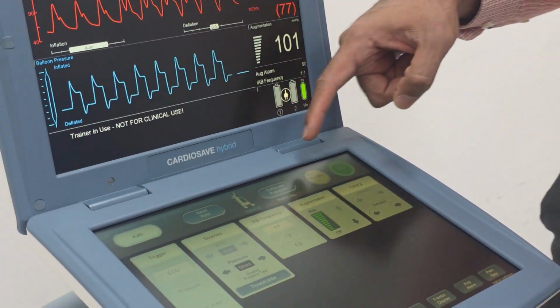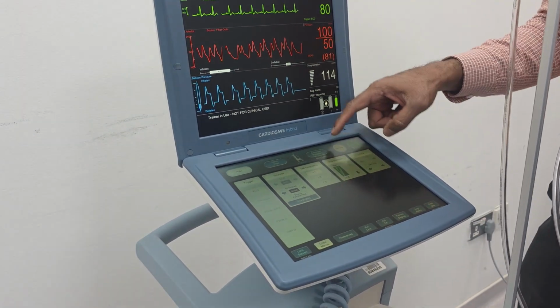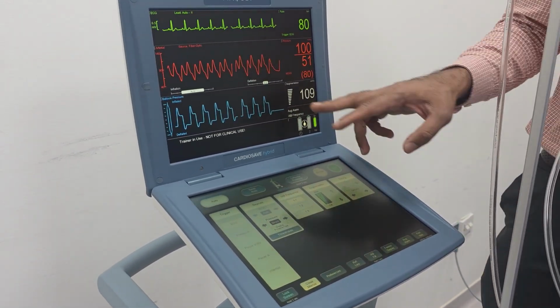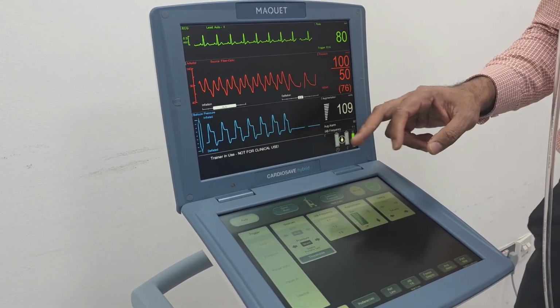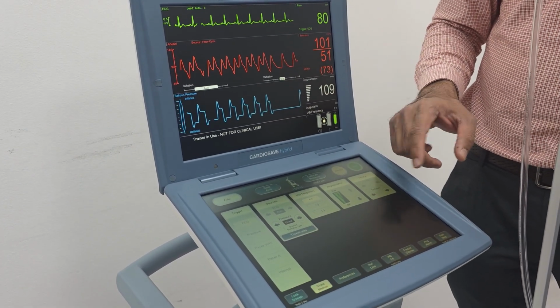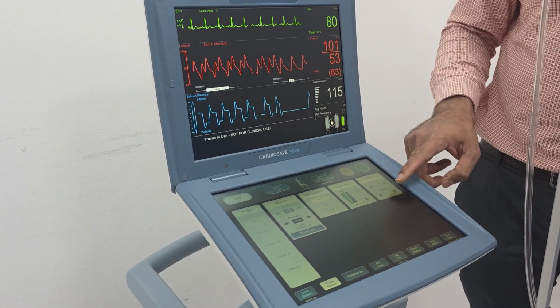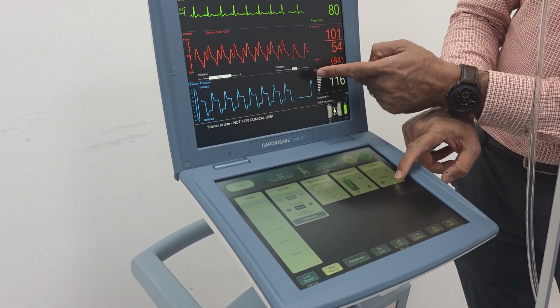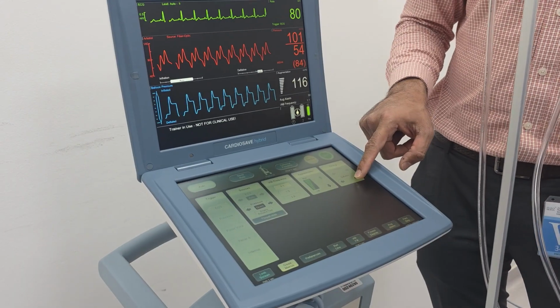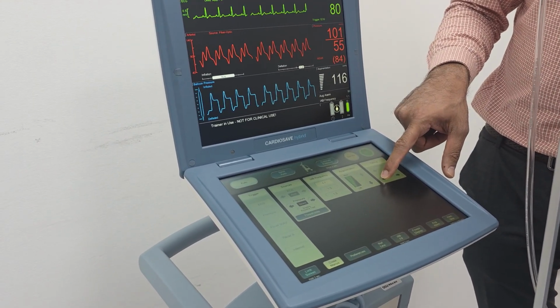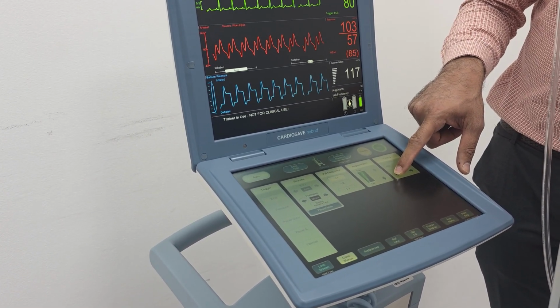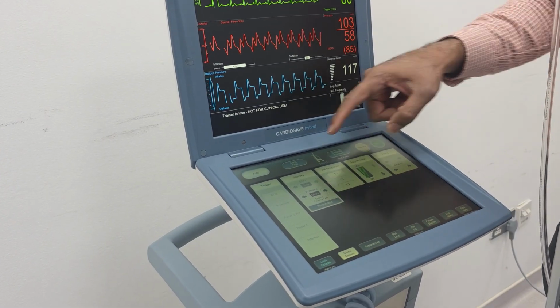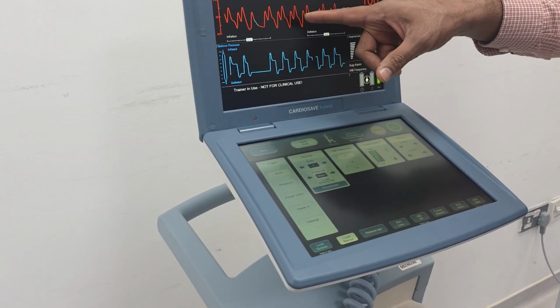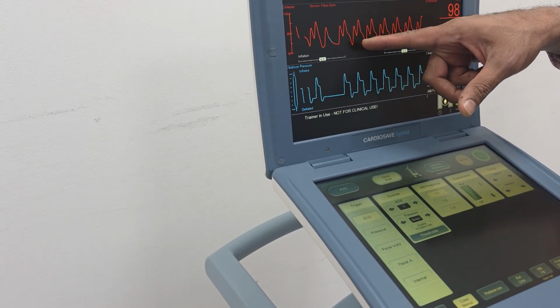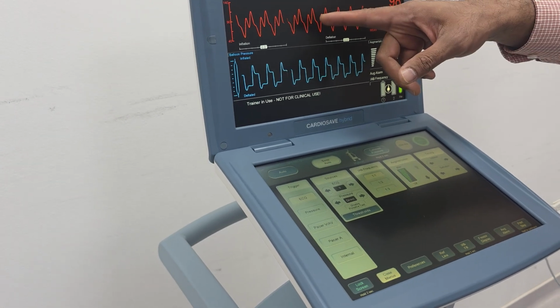Now I will go to auto mode again. In auto mode, you don't have any control on the timing. See, both are in auto. When to inflate and when to deflate, the machine is controlling automatically. But in auto mode, you can still control the deflation when the balloon is deflating, if you want. It's just advanced information, to explain what the clinical controls are. But in semi-auto mode, if we start pumping, we can also delay the deflation. Now you cannot see the dicrotic notch here, right? You cannot see the dicrotic notch here.